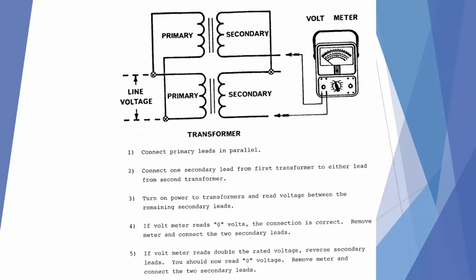To make sure your transformers are properly phased together, you will need your voltmeter to check the voltage coming out of the secondary side of the transformer. So take two of the leads coming off the secondary and tie them together, and then with the other two leads that are open, you will put your voltmeter across them. Apply voltage to the transformer, and then if the voltmeter reads 0 volts, the connection is correct. Remove the meter and connect the two secondary leads. However, if the voltmeter reads double the rated voltage, reverse the secondary leads. You should now read 0 voltage. You can remove the meter and connect the two secondary leads, and your transformers will be properly phased.